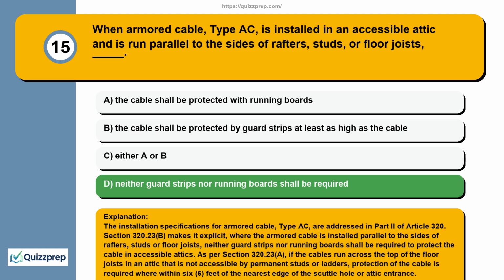The installation specifications for armored cable, type AC, are addressed in Part 2 of Article 320. Section 320.23(B) makes it explicit: where the armored cable is installed parallel to the sides of rafters, studs or floor joists, neither guard strips nor running boards shall be required to protect the cable in accessible attics. As per Section 320.23(A), if the cables run across the top of the floor joists in an attic that is not accessible by permanent stairs or ladders, protection of the cable is required where within 6 feet of the nearest edge of the scuttle hole or attic entrance.